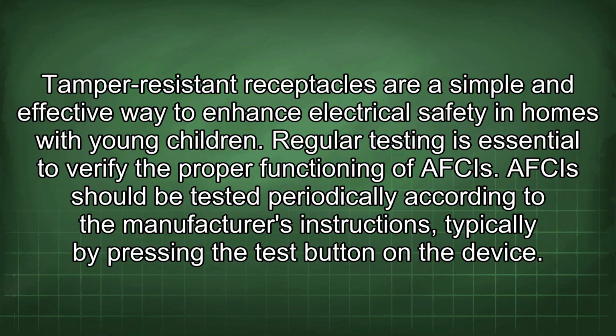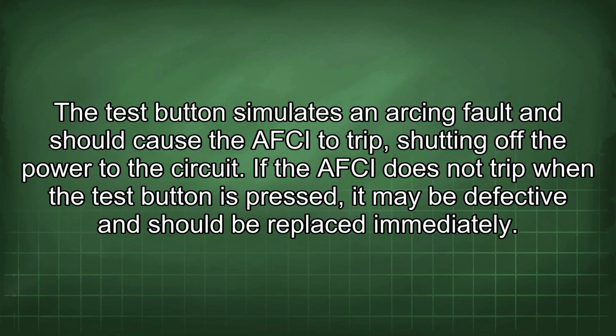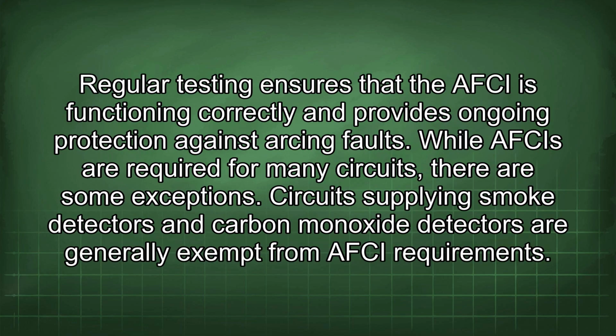Regular testing is essential to verify the proper functioning of AFCIs. AFCIs should be tested periodically according to the manufacturer's instructions, typically by pressing the test button on the device. The test button simulates an arcing fault and should cause the AFCI to trip, shutting off the power to the circuit. If the AFCI does not trip when the test button is pressed, it may be defective and should be replaced immediately. Regular testing ensures that the AFCI is functioning correctly and provides ongoing protection against arcing faults.